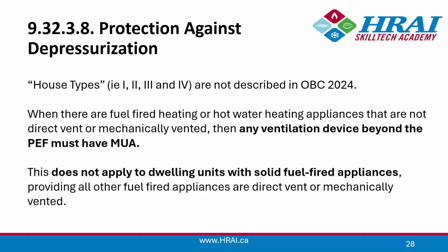When there are fuel-fired heating or hot water heating appliances that are not direct vent or mechanically vented, then any ventilation device beyond the principal exhaust fan must have makeup air.